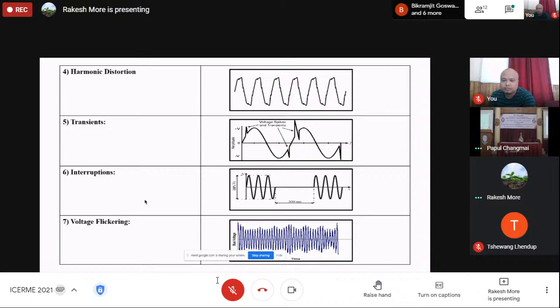Sometimes a transient occurs in the voltage wave. When a sudden change occurs in system voltage, some variation is found in the steady state condition of the voltage, whose frequency is different from the power frequency. These changes are known as transients. Transients come under short duration events. The detection of transients is difficult, as the conventional meters used for monitoring purposes are of limited frequency.